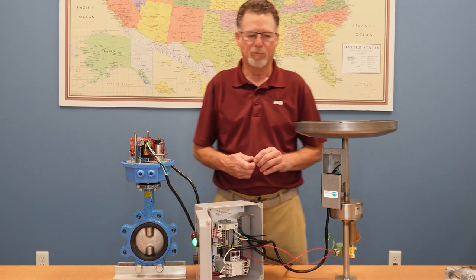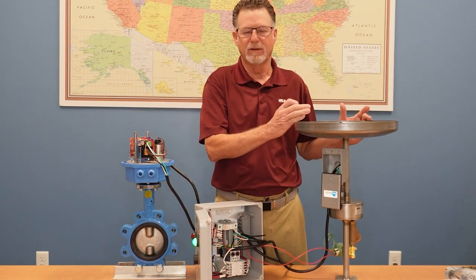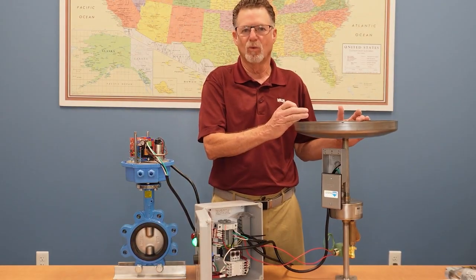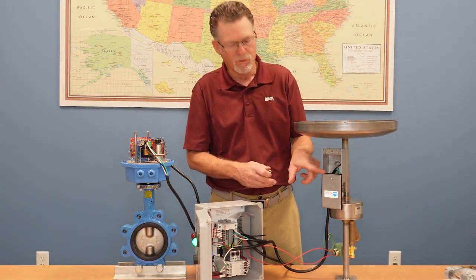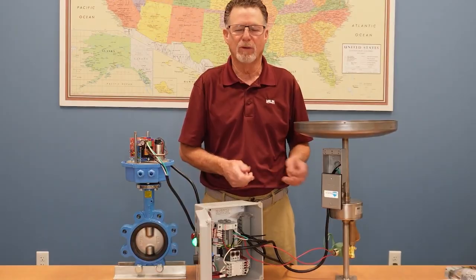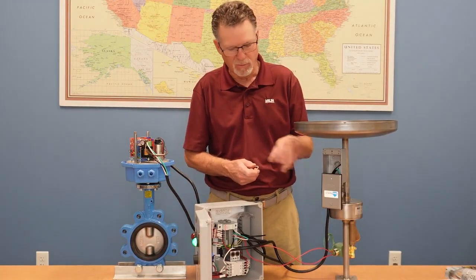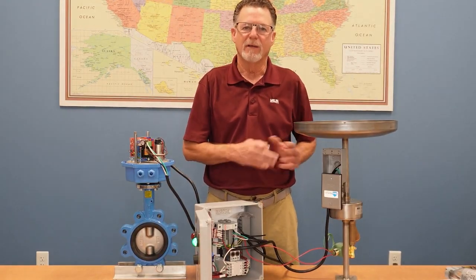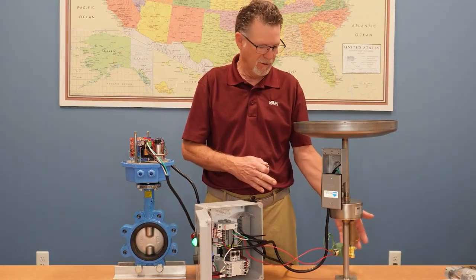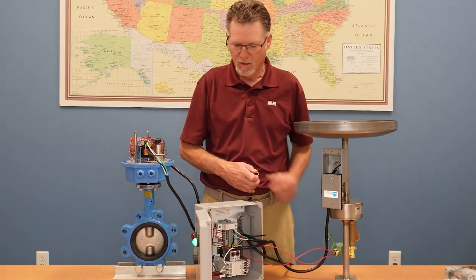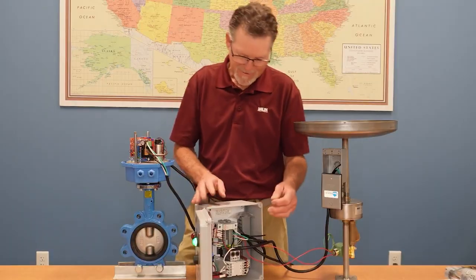So if you're having a problem, the first thing you want to do is verify that the RainSwitch is working. Make sure you've got 12 volts to the probe, between ground and the probe, the top of the probe where the connection is. If that's all right and everything's clean here, then you go to the pilot station.